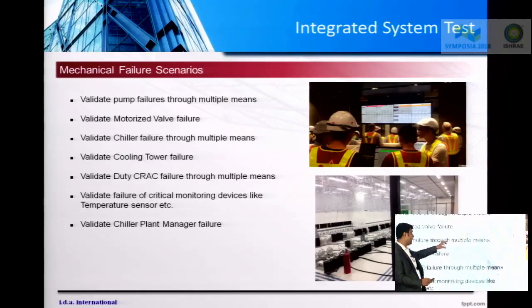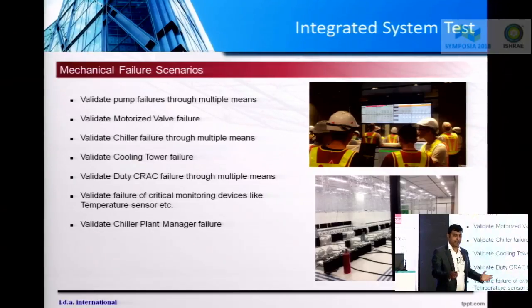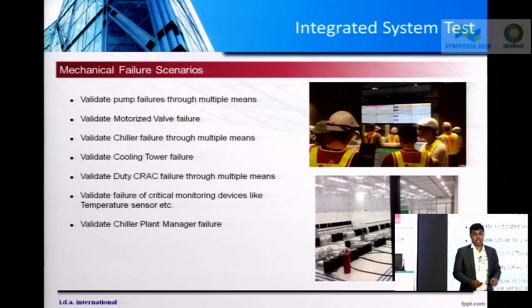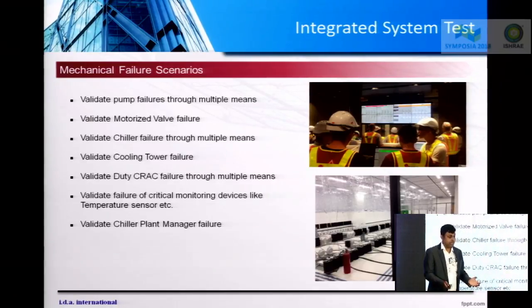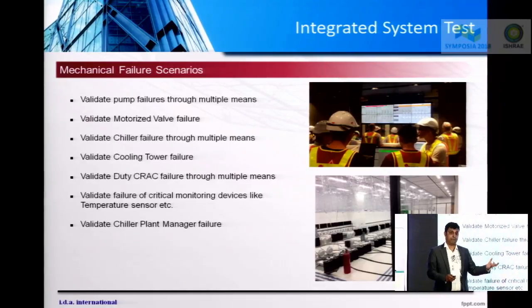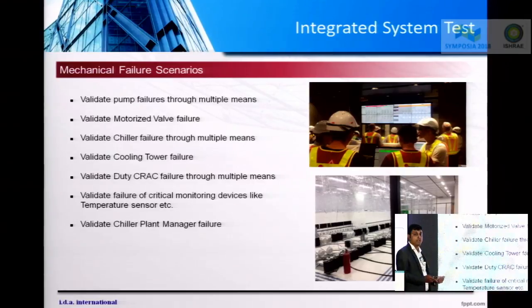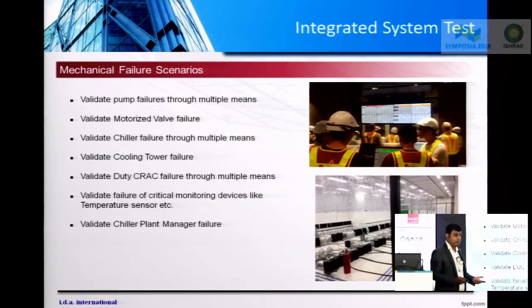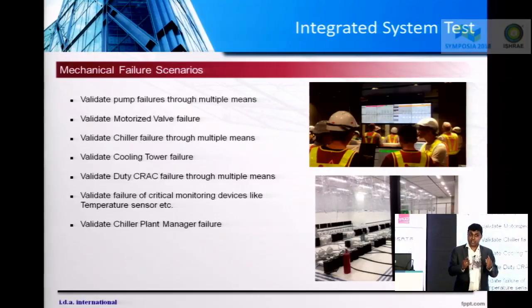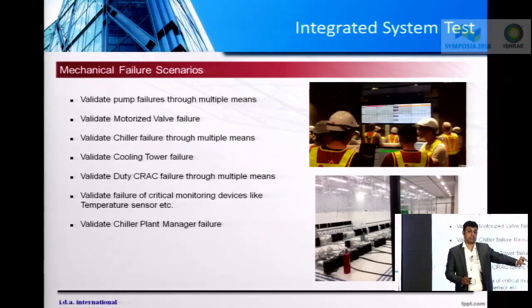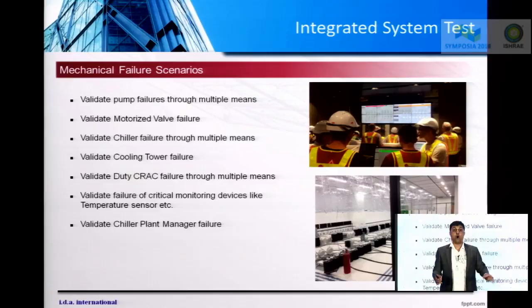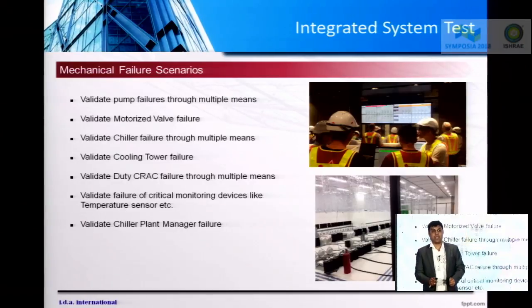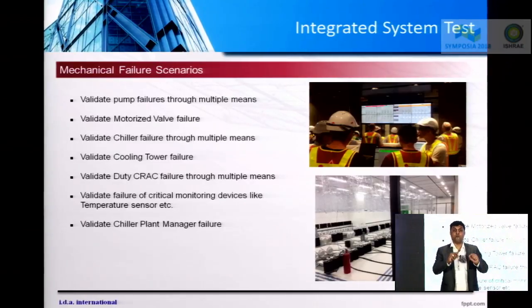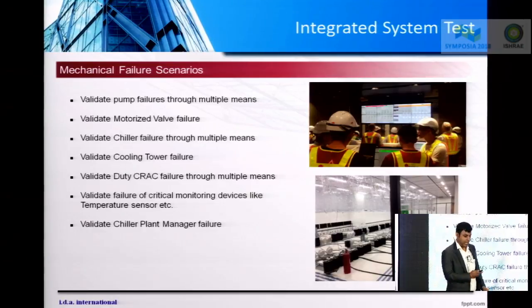So what could go wrong in your mechanical system, in your chiller plant? The first point is, I could fail a pump through multiple means and see what happens. I could fail a motorized valve, a chiller, a cooling tower, a CRAC unit. I can even fail a temperature sensor which is controlling your chiller plant, or a chiller plant manager which is creating the logic for the chillers to operate. So I have to try my level best to observe what could go wrong in a data center. How do I do it?